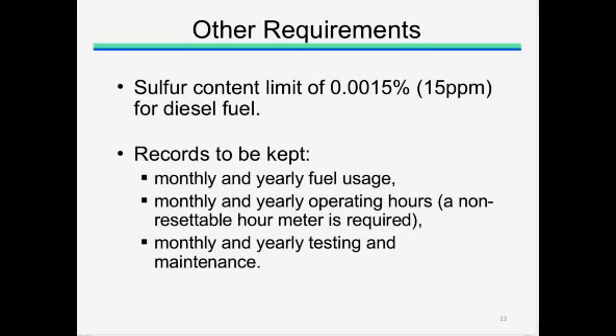If a state were to adopt the rule, it would require all shipments of diesel fuel that are received for use in a diesel-fired stationary generator to have a sulfur content of 0.0015% or 15 parts per million, which is also typically known as ultra-low sulfur diesel fuel. As for record keeping, the model rule requires monthly and yearly records for fuel usage, operating hours, and hours when testing and maintenance are performed.